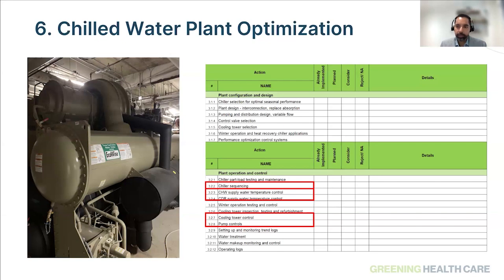Are they loading correctly? Are you having to run only one chiller based on the outside conditions, or are both chillers coming on and wasting energy? Is your supply water temperature too low, because that impacts your chiller efficiency as well? Similarly, is the condenser water temperature set too high? Those are minor modifications you can make in your controls, working with your controls teams to improve the chiller optimization.